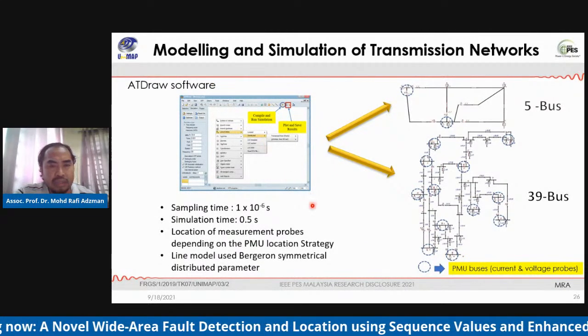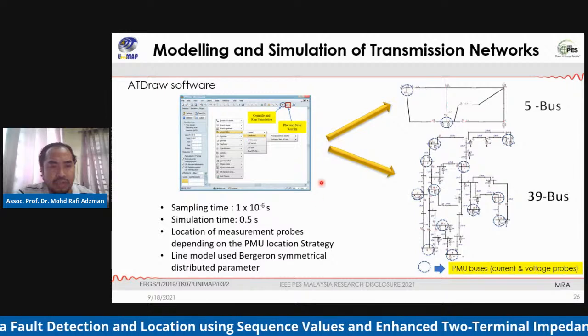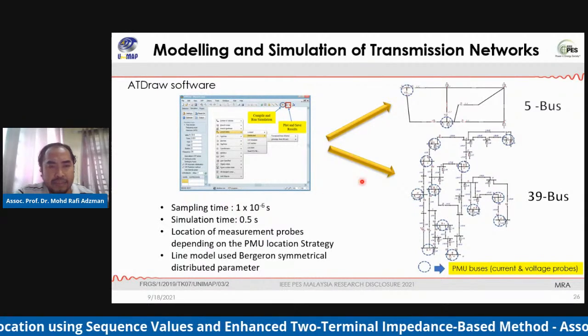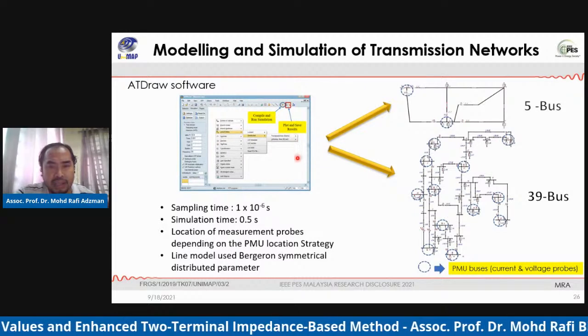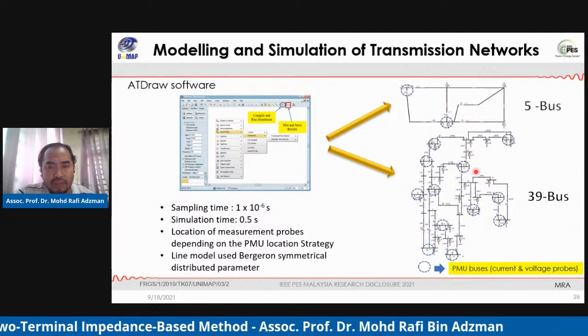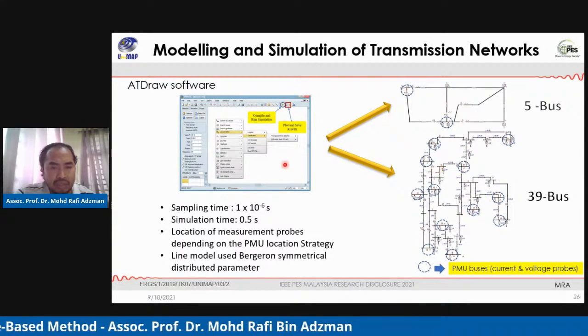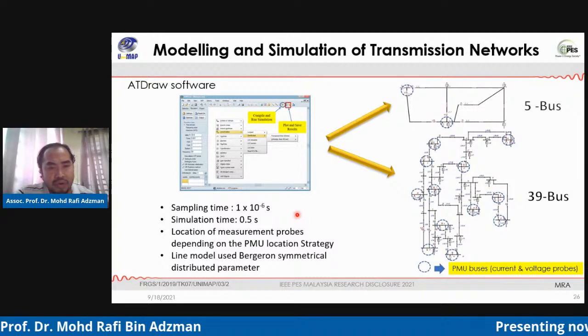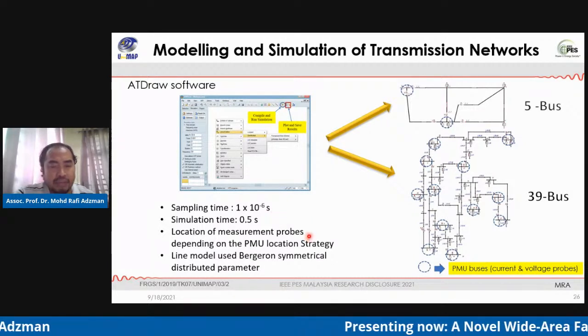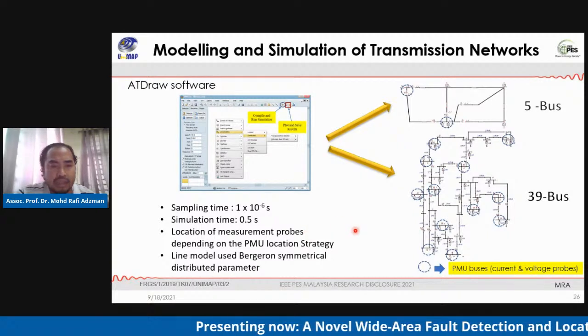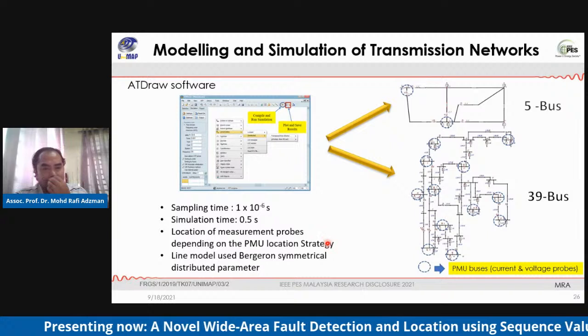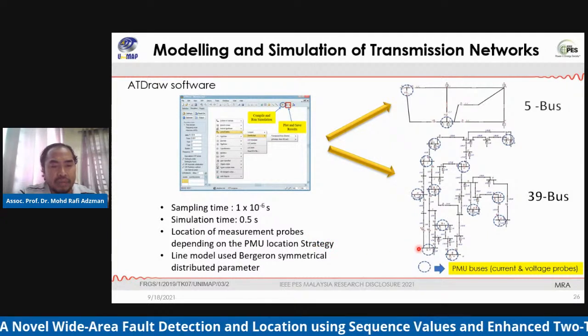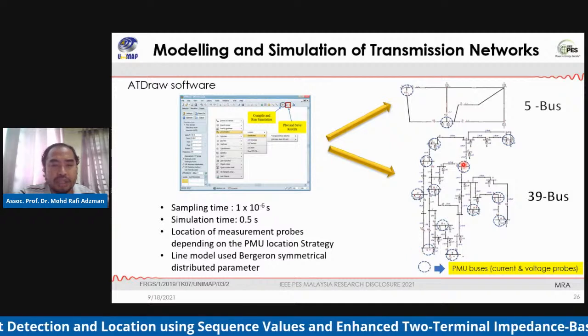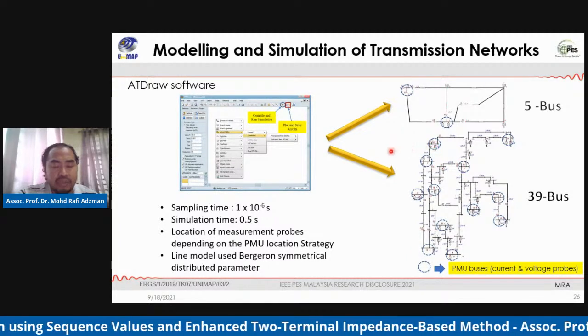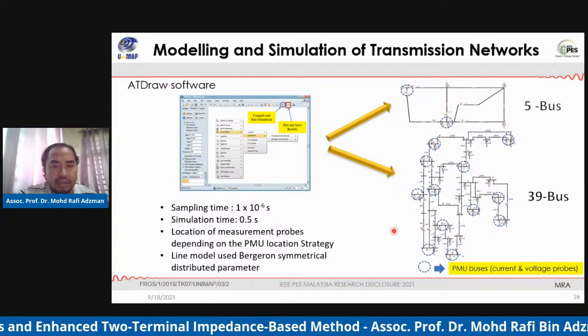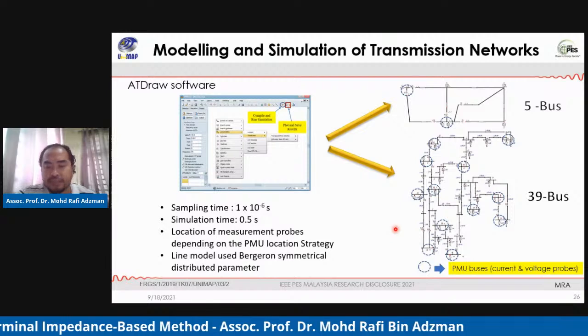So this is the model and simulation of the transmission network. We use the ATPDraw software, starting with a blank canvas. Then we start modeling the 5 bus and also the 39 bus networks. For this simulation, we use a sampling time of 1 times 10 to the power of negative 6 second, and the simulation time is 0.5 seconds. The location of measurement probes depends on the PMU location strategy. The line model that we use is the symmetrical distributed parameters type.